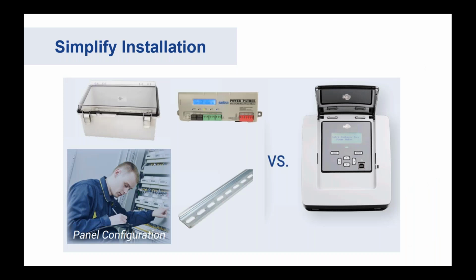The other thing was about simplifying installation. A kind of hidden cost factor within submetering is that if you have a meter like our Power Patrol, there was always a cost to installing it within a panel that was often hidden at bid time. With that, we mean that we used to have a customer buy a separate panel, either a plastic enclosure or metal enclosure. They would buy this enclosure, put a backplate in it most of the time, put a DIN rail into it most of the time, snap the Power Patrol in, and all that's before getting to the job site.